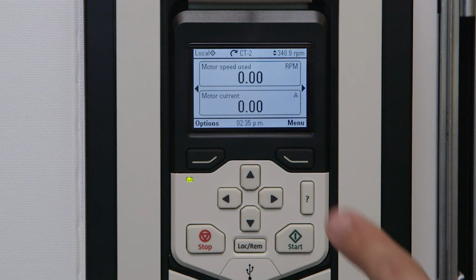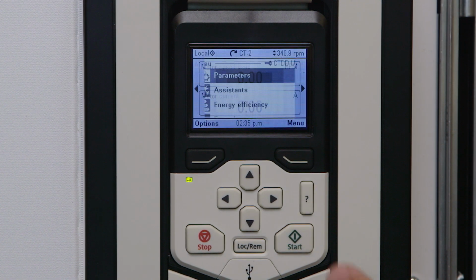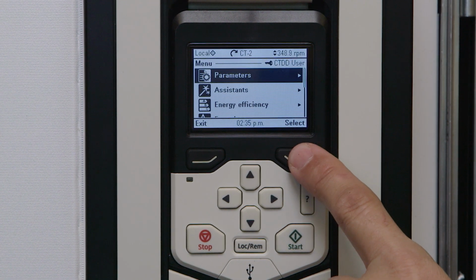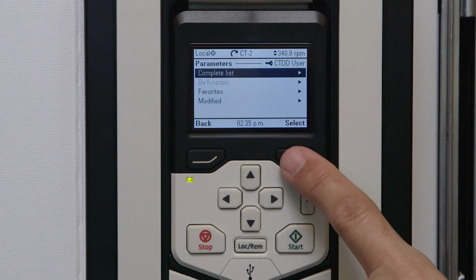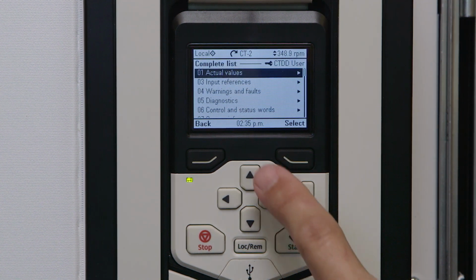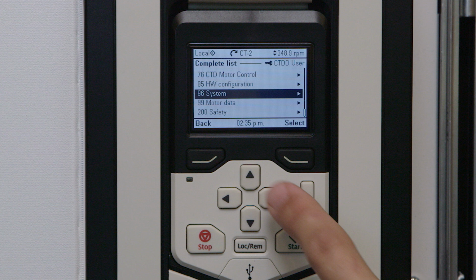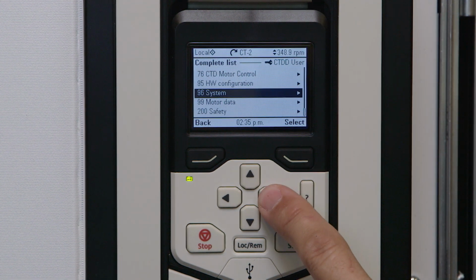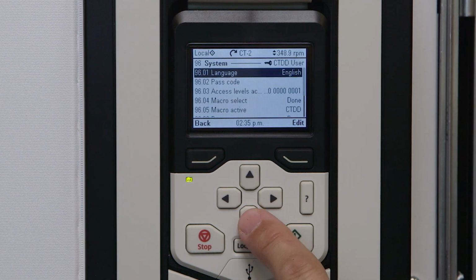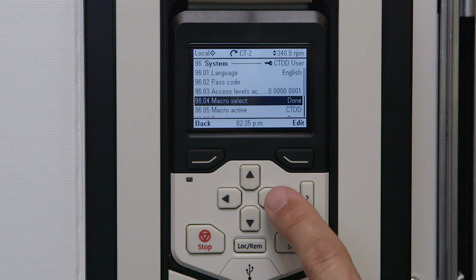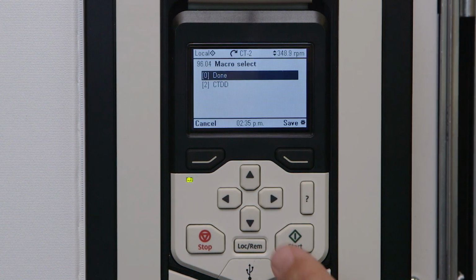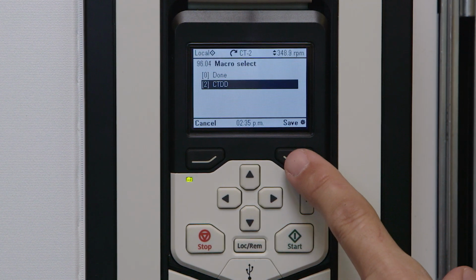Sometimes someone has pressed too many buttons before you, and you want to reset the VFD back to factory defaults. To reset the VFD parameters back to the default settings, you will need to change parameter 96.04 macro select to a value of CTDD and then press Save.